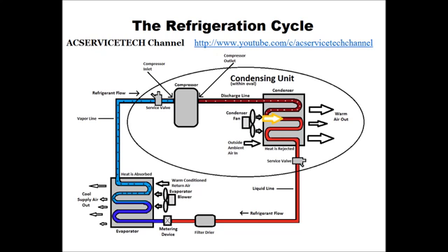It comes from the saturated state in the middle of the condenser coil and continues to reject heat as a complete liquid until it comes out of the condenser coil. Then it comes down in the picture here, makes a left, and goes in through the filter dryer. The filter dryer is there to absorb any moisture in the system. It has a fixed capacity, and that's it. It comes through that, and then it hits the metering device.